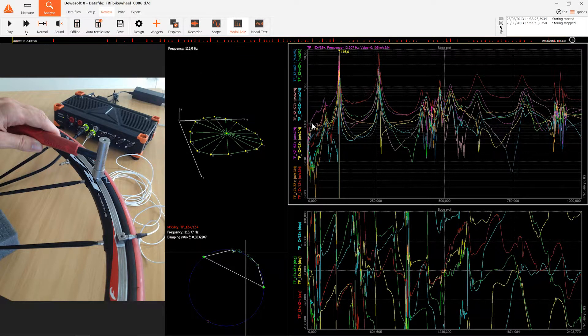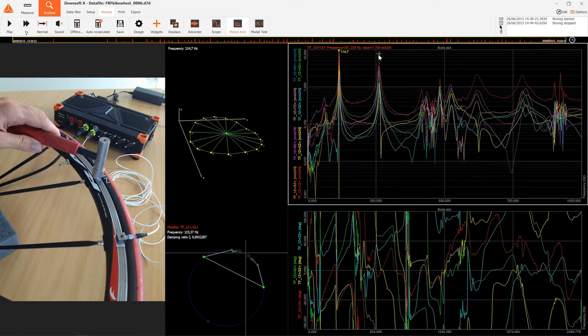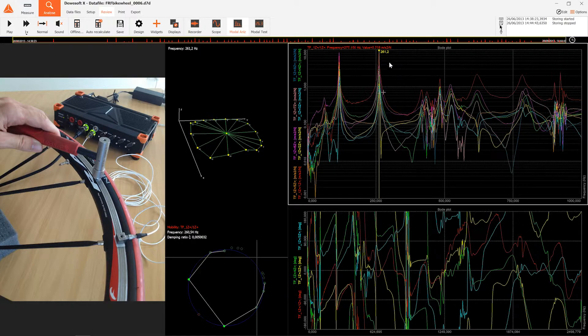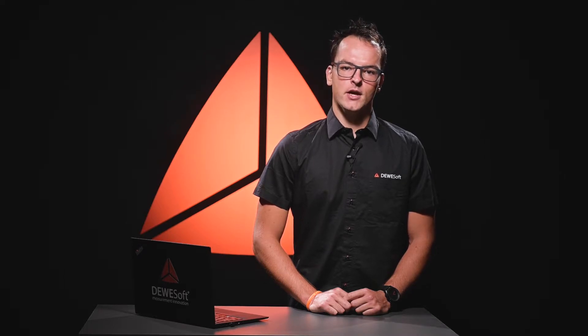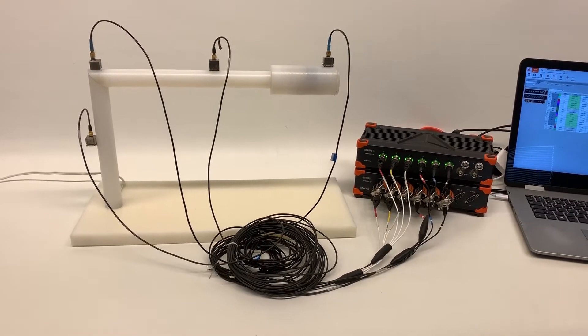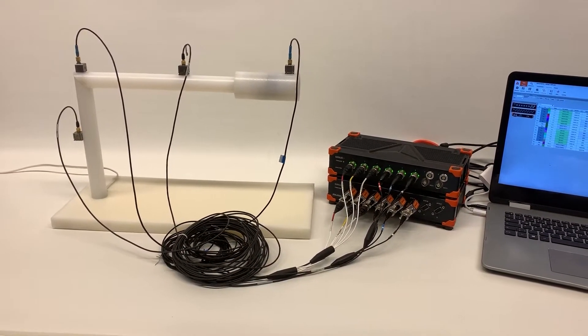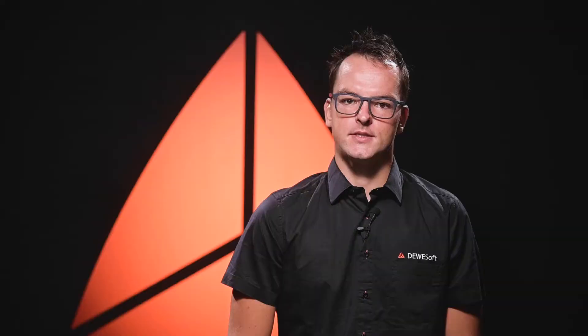With Dewesoft's modal test solution, you are able to excite the structure with an impact hammer or shaker and easily measure the responses with our dual core technology. With dual core technology, we can achieve 160 dB dynamic range in time and frequency domain with up to 200 kHz sampling rate per channel. When performing the measurement with an impact hammer, the software allows grouping, rejecting, and repeating measurement points.